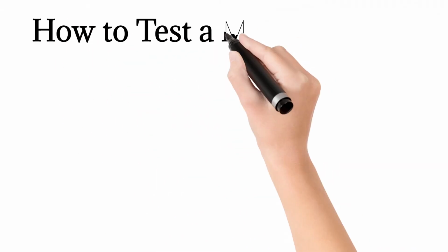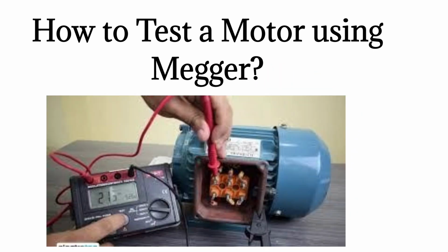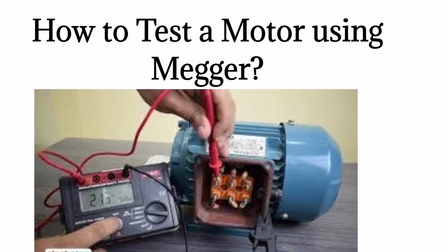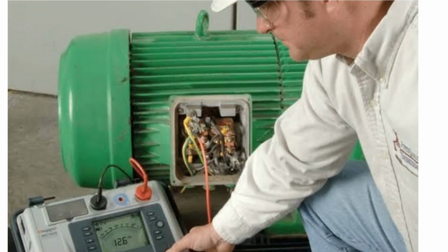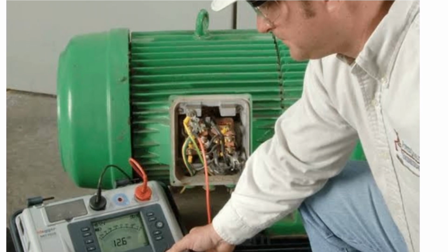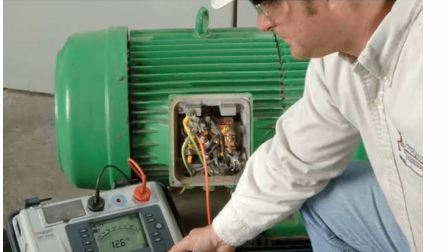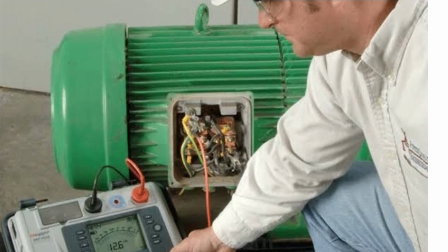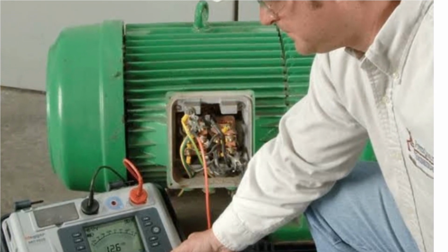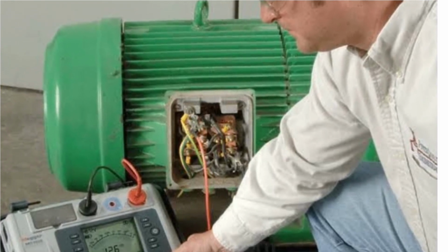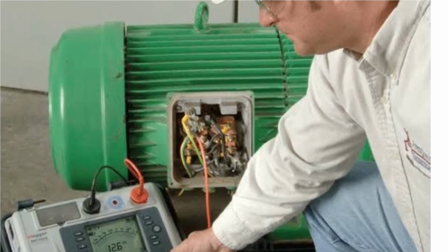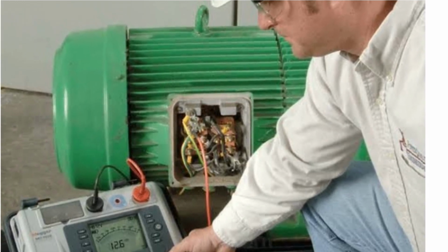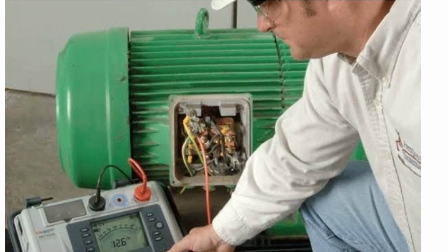How to test a motor using Megger. Disconnect the motor from the power supply and connect a Megger between the windings. Establish a safe working zone to keep away unauthorized personnel from the Megger, as it will be supplying a high voltage. Incorrect use of Megger can cause damage to the parts of the equipment and injuries to users.